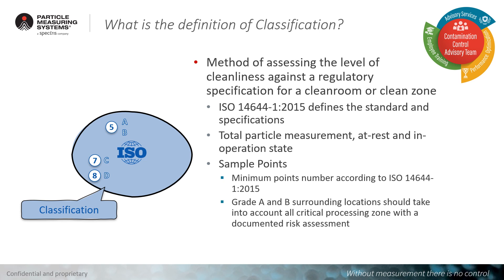The first question that we must ask is: what is the definition of classification? The draft report is more or less the same definition that we can find in the ISO 14644 Part 1, published in 2015. The classification is a method of assessing the level of cleanliness against a specification. The ISO gives the specification that we must comply with.